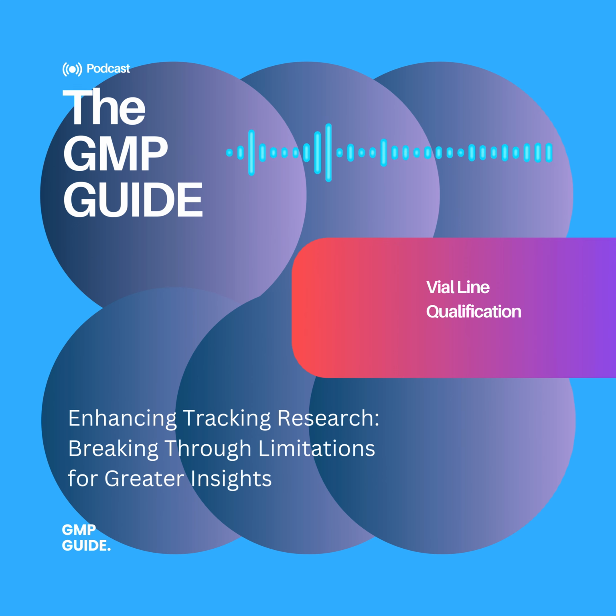This must precisely match the design specifications and the manufacturer's installation checklists. Essentially, IQ ensures the system has the necessary prerequisite conditions to function as expected. It's about meticulously checking every physical connection, every wire, and every software setting, getting the physical setup right. You've hit on the essence. The key focus areas for IQ are incredibly thorough because it's the birth certificate of your system, as you said.